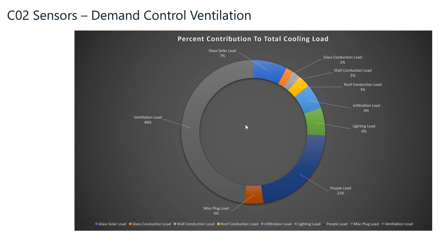And the reality is, with the CO2 sensors and demand control of ventilation, we cut our ventilation air substantially down throughout the building, especially when the building isn't fully occupied to its planned capacity, or even during modes where we have partial students in the building. So controlling the amount of ventilation air is a substantial way of saving energy within a facility like this.